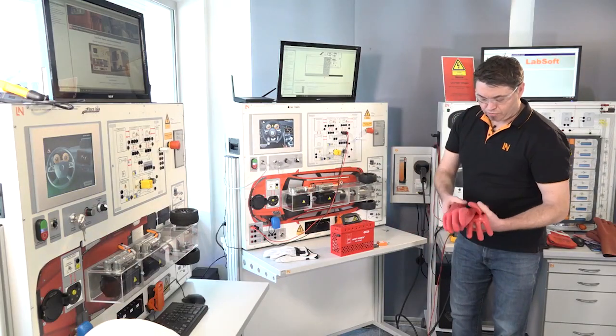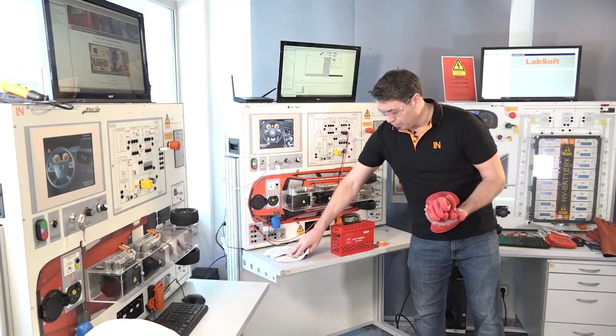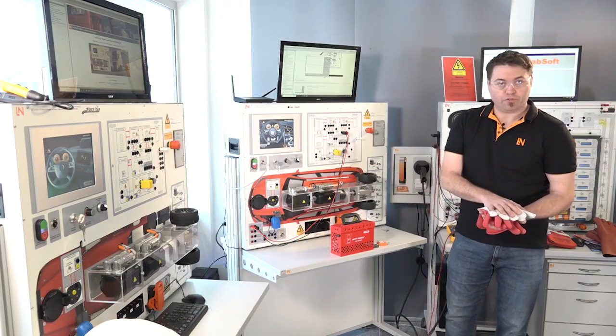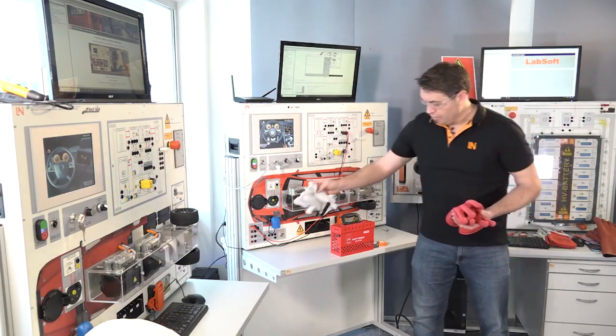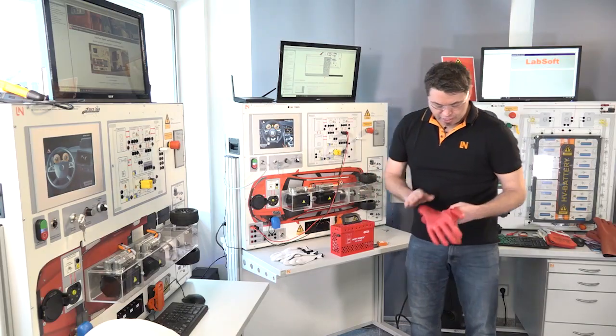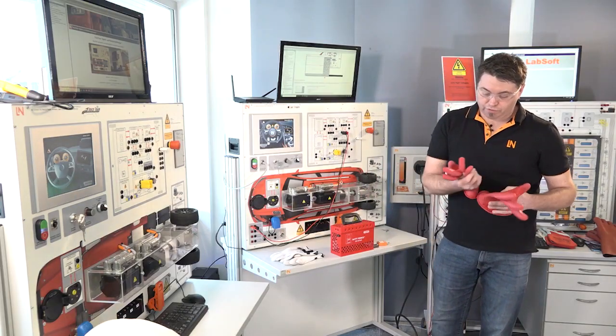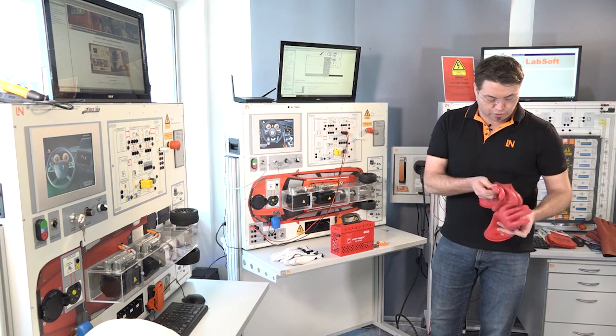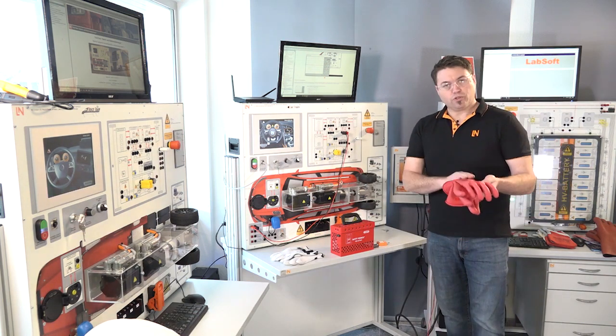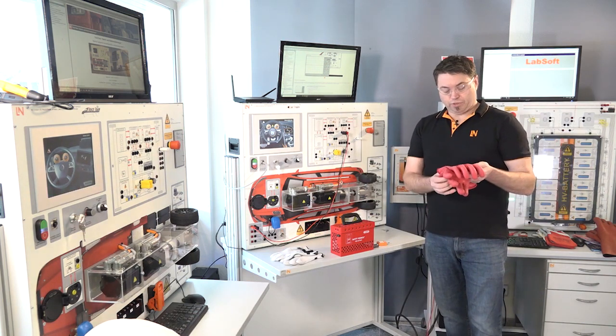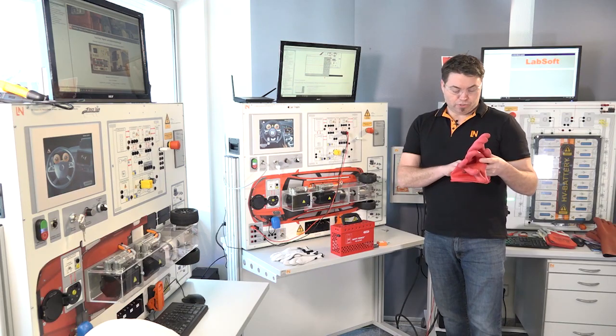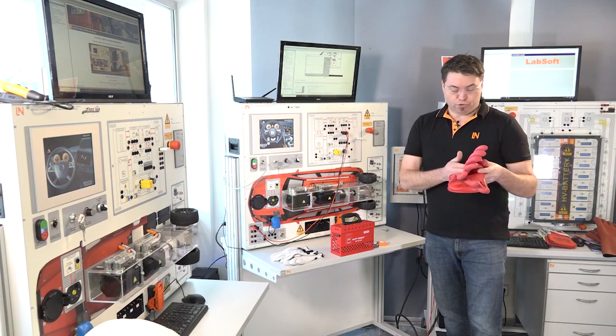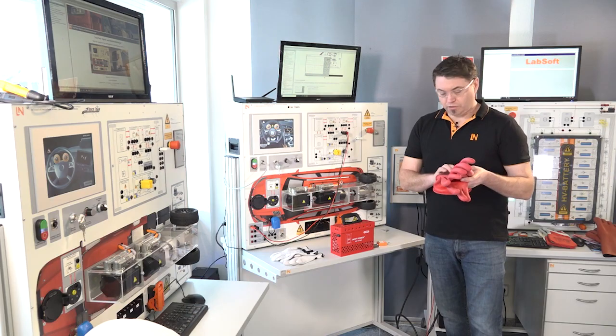And also our gloves, high voltage gloves. In this case we're going to use leather over gloves as well. There's a number of things we need to test first with our gloves, to make sure they're in good condition, which these ones look like they are. We also need to make sure the date is within date, so when was the last time they were tested. We fall within 6 months, so these are okay to use.